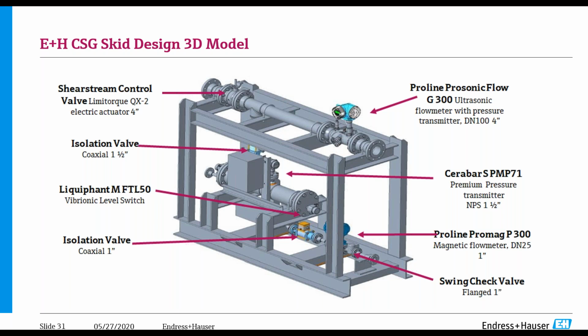Another aspect of coal seam gas is it's a wet gas, and we very often get water carryover, even coming up into the gas line. And this is predominantly happening when you have process step changes or process upsets. But the flow meter itself is very well designed to, first of all, handle wet gases, but also by design has drainage facilities inside the transducer sockets to avoid the bridging that Jason was talking about earlier, bridging between the transducer and the inside body of the flow meter itself. So there are some key points there.